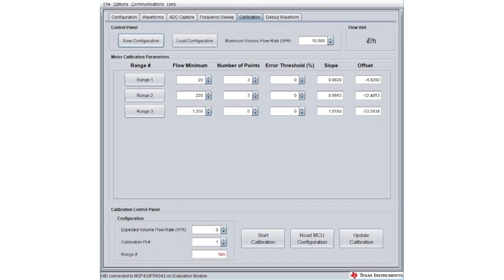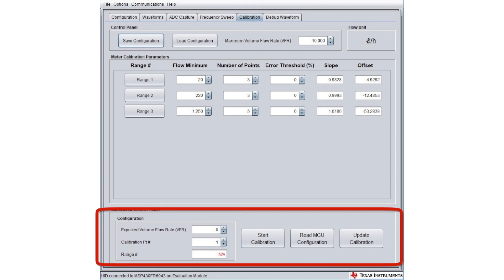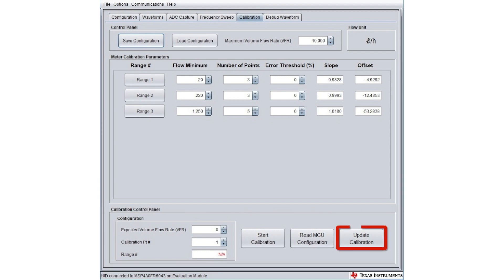The calibration tab enables you to calibrate the meter for different flow ranges. The number of ranges is defined in the configuration tab prior to generating the code. At runtime or manually, you can input calibration test points for each range. This allows the GUI to calculate the linear meter constants per range, which results in increased volume flow rate accuracy. Once the constants are calculated, click the Update Calibration button to write the calibration values to the device.